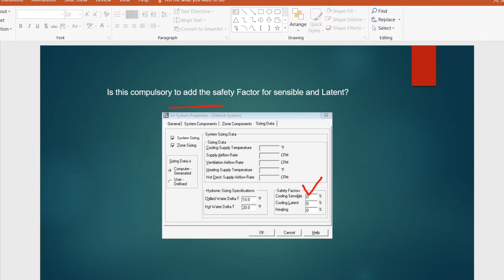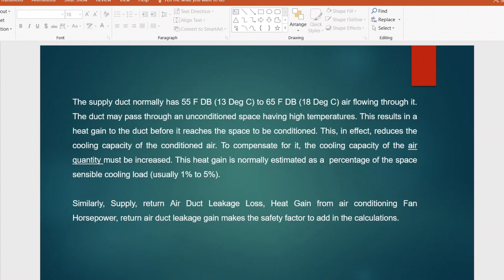The next question for HAP cooling load calculation: is it compulsory to add a safety factor for sensible and latent loads? The supply duct has air flowing at 55°F to 65°F (13°C to 18°C) and may pass through unconditioned spaces at higher temperature, resulting in heat gain to the duct before it reaches the conditioned space. This reduces cooling capacity, so the cooling capacity must be increased. This heat gain is normally estimated as 1 to 5%. Additionally, supply and return duct leakage, heat gain from the fan motor horsepower, and return air leakage all make it necessary to add safety factors.